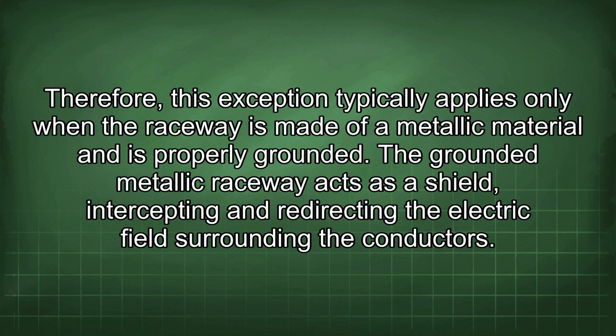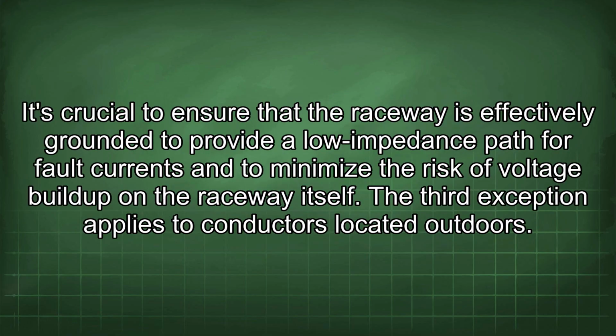The grounded metallic raceway acts as a shield, intercepting and redirecting the electric field surrounding the conductors. It's crucial to ensure that the raceway is effectively grounded to provide a low-impedance path for fault current and to minimize the risk of voltage buildup on the raceway itself. The third exception applies to conductors located outdoors.